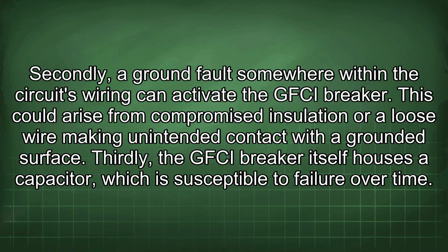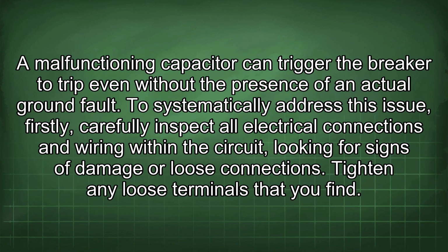This could arise from compromised insulation or a loose wire making unintended contact with a grounded surface. Thirdly, the GFCI breaker itself houses a capacitor, which is susceptible to failure over time. A malfunctioning capacitor can trigger the breaker to trip even without the presence of an actual ground fault.